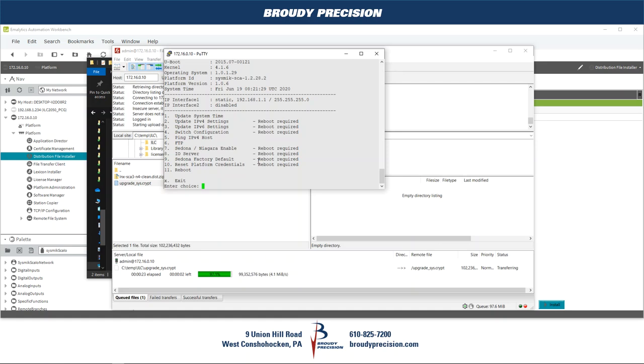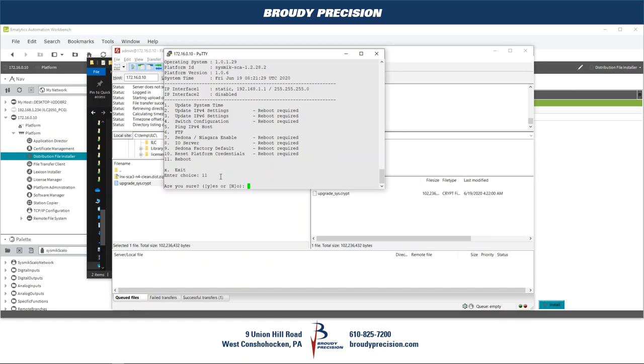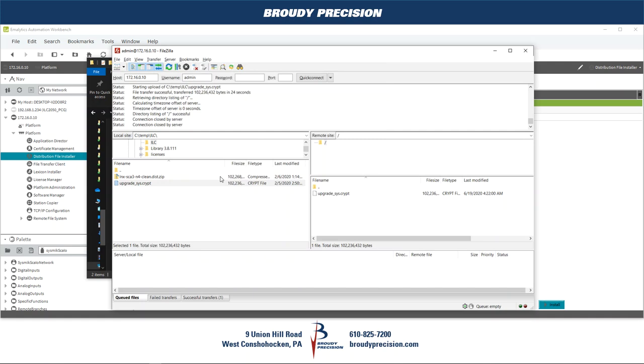Now that the file transfer is done, go back to the shell, choose option 11 reboot, confirm yes, and the controller will go through the process of restoring all factory defaults. It puts in a clean image — wiping everything: the station, modules, everything that was in there. It resets platform credentials — username and password — and also resets the passphrase, which you can re-enter once you log in with platform.